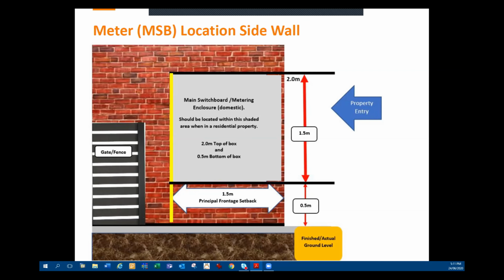So the meter panel, what you're saying, the bottom of the meter, so meter readers can access it, or are you saying the entire panel? Yeah, basically, if it's a freestanding board, then it's the entire panel. But it depends on the circumstance of that sort of board. If you took a standard type 1 or type 2 board and freestanding mount, the intent is the bottom of the box is half a metre off the ground, so that somebody working on it isn't sitting on a low stool to do any work. Okay, thank you. Thanks.